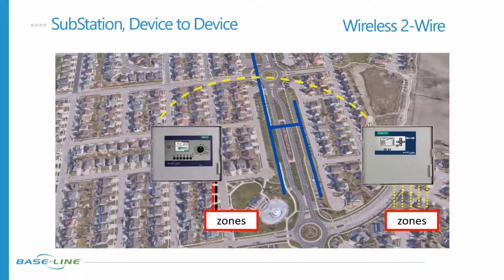One of the things I usually use to describe how this works—at least half of the people on this call probably know how our two-wire works in terms of the search and assign capability, and how that is so powerful. It works the same way. So if you hook two-wire up to zones and want to bring those into the 3200 controller, you turn the dial to search and assign, run a search, and it uses the wireless protocol, but it's still that two-wire search and assign capability that brings those into the controller.